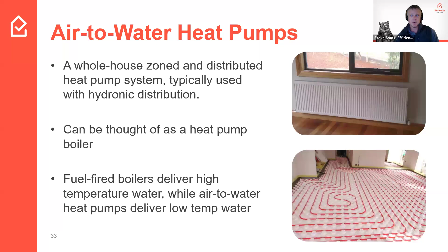So utilizing an air-to-water system, you do have a lot of flexibility in how you distribute that heat energy into the home. With an air-to-water system, because of that heat exchange and the fact that you're just maintaining a tank of hot water with that heat pump, you can provide distribution through forced air. So you can have a coil of hot water in a forced air ducted system, distributing your heat energy that way. More commonly, and most predominantly with air-to-water systems, you're using hydronic distribution. So that would be what Bob mentioned earlier: baseboard heaters, radiant heat, radiators.